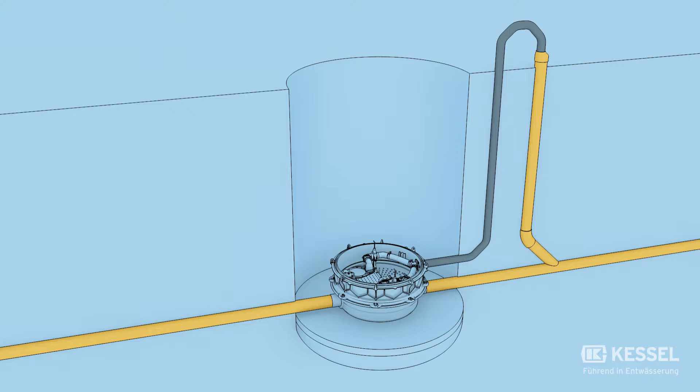In this step, we install the pressure line above and beyond the backflow level and connect the individual line parts by means of a hot plate or electro welding process.